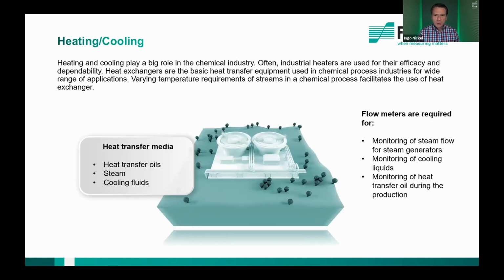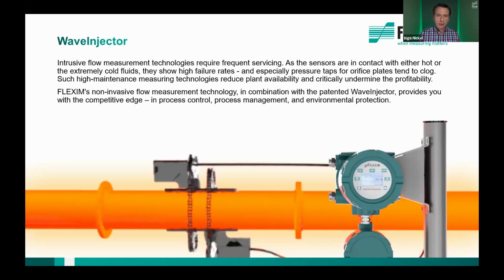Depending on the process or the chemical reaction, heat must be transferred within parts of the plant. Some chemical reactions or processes need additional energy to run effectively. On the other hand, exothermic reactions require an effective energy management system to remove excess heat from the process to avoid critical situations. Heat can be transferred by heat transfer oil, steam, or cooling fluid within chemical plants. Typical measuring tasks are monitoring of steam flow, heat transfer oils, and cooling liquids.